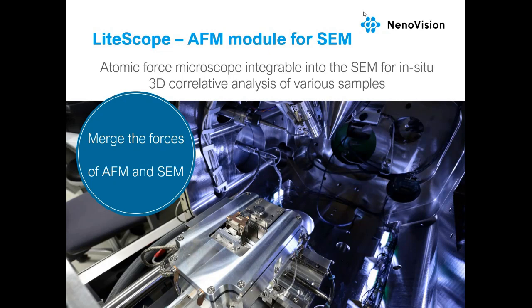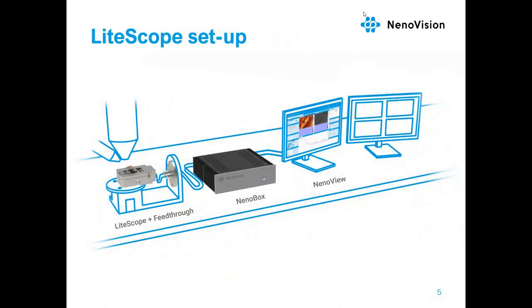Correlative sample analysis combining atomic force microscopy and scanning electron microscopy is achieved by integrating the compact atomic force microscope called LiteScope into the scanning electron microscope chamber. Integration is quite easy — LiteScope is installed on the SEM stage, and the signal goes to the controller NenoBox, which is accessible via Wi-Fi or internet. Both SEM and AFM software are operated from the same computer.